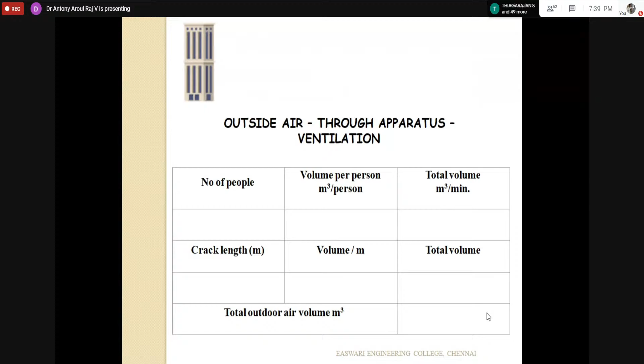Then we have to calculate how much will be the outside air through the apparatus for ventilation. Take the number of people, multiply as per ventilation standard how much is the meter cube per person, so I get the total volume. Similarly, take the crack length, through that 1 meter crack find how much volume, multiply that to find the total volume per minute. It's very important - I give it as meter cube, but you have to put it as meter cube per minute, because everything is based on rate only - what is the rate of heat entry into the room. That is what I am trying to convince today.